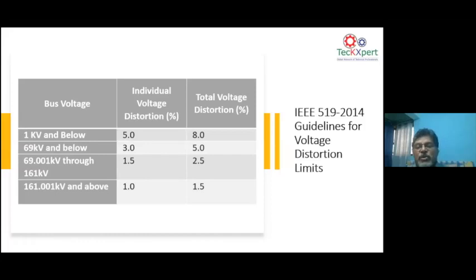As you all know, IEEE 519 defines what is the harmonic distortion permitted in terms of individual and voltage harmonic, as well as for all the low voltage network. The latest IEEE 519 says that you can go up to 8% voltage distortion, but at an individual level, you can go only up to 5%. Now, if you go higher than 400 volts, if you go to 66 kV, 11 kV, 33 kV and all that, the individual voltage distortion permitted is around 3%, but total voltage distortion you can go up to 5%. This is IEEE 519.